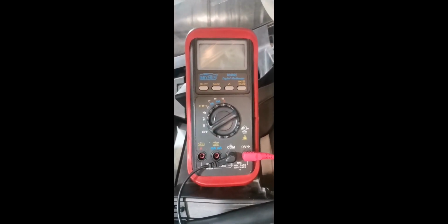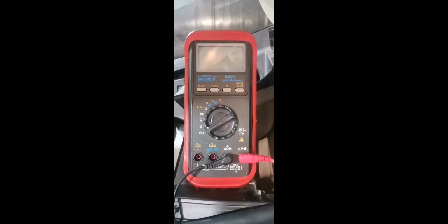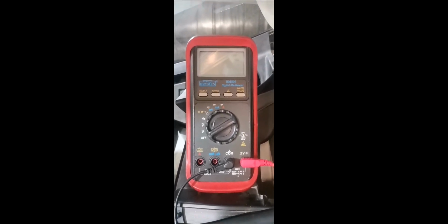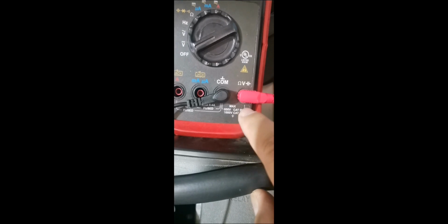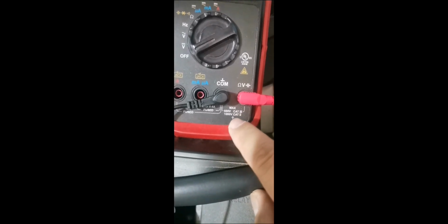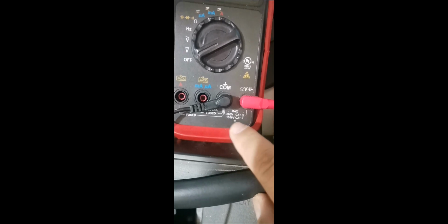Before measuring the high voltage capacitor, see to it that your multimeter is capable of high voltage measurement. That is why on the lower part you have your multimeter class indicated. This multimeter should be at least cat 2. Cat 2 can measure up to 1000 volts. Do not use a multimeter lower than this specification, we need at least cat 2 to measure the high voltage capacitor, or else our multimeter will be damaged.